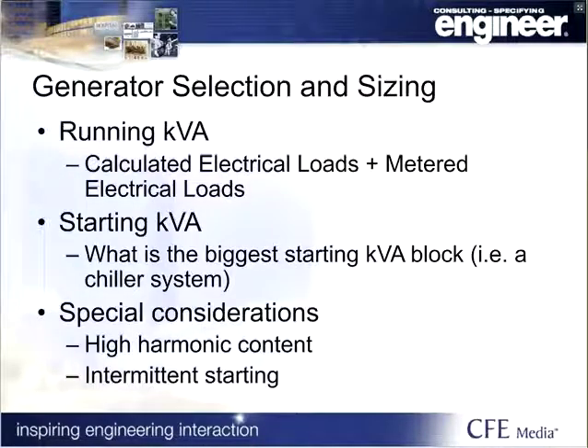So generators are sized on a couple basic blocks. You're going to talk about the running kVA, which is basically your operating load. You're going to talk about the starting kVA. So if I have a big chiller that's going to start up, whether it's a cross-the-line starter or a VFD that's going to slowly ramp up the load, that certainly makes a difference on my generator, whether or not it can handle that starting kVA.